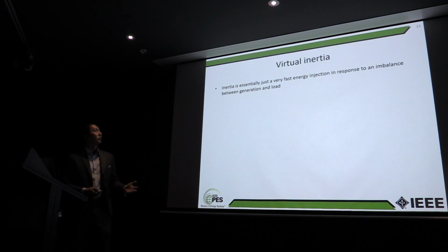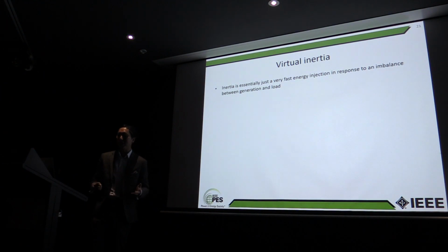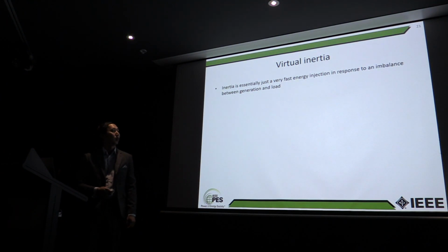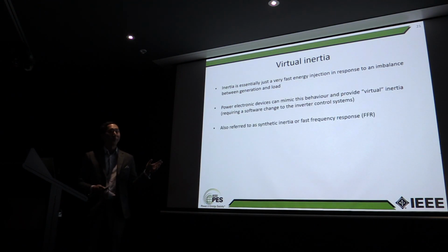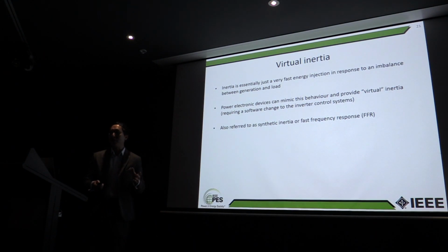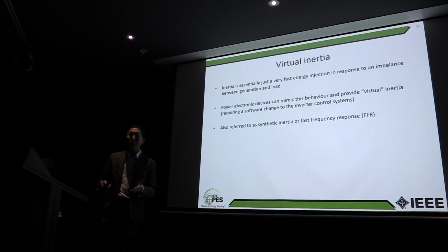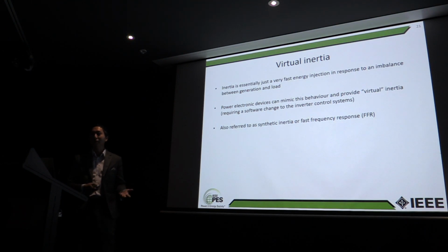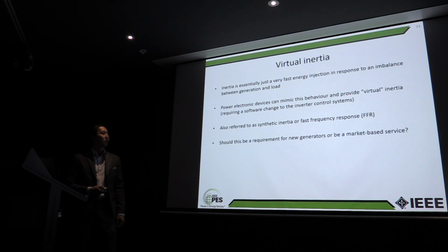So yeah, virtual inertia. As we've just discussed, inertia is essentially just a very fast energy injection at 0 seconds, in response to an imbalance between generation and load. Now, these power electronic devices can mimic this same behavior and provide a virtual inertia. You basically have a battery or a wind turbine with some headroom, and you can inject that power in very quickly. It requires a software change, though, to the control systems of these inverters, but you could technically do it, and it's sometimes referred to as synthetic inertia or sometimes fast frequency response as well. Now, this is up for discussion, possibly a bit contentious. Should this be a requirement for new generators, or should this be market-driven? It is a question for us to discuss.